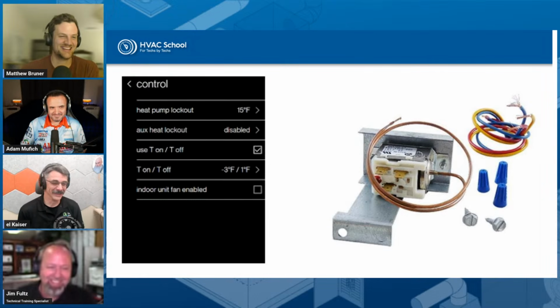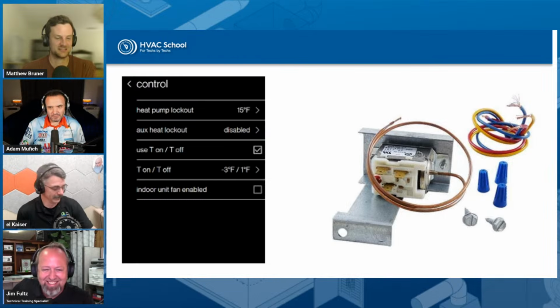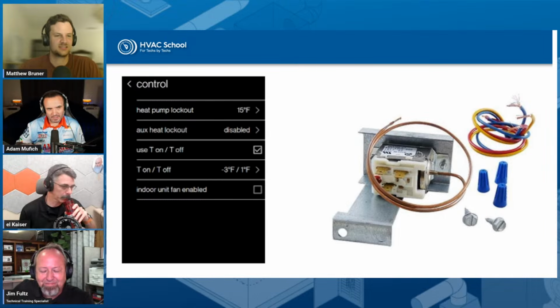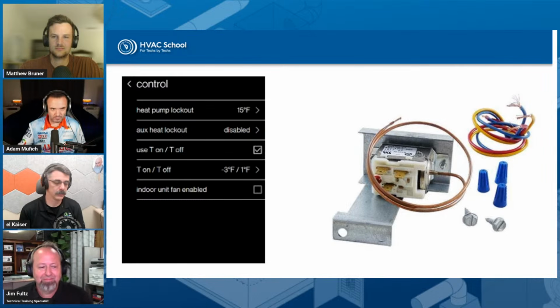I think in Manual T they refer to it as an occupied zone and an unoccupied zone, and you are not supposed to by any means blow any air into an occupied zone. It should be in a place where humans don't inhabit in the home, right? And that occupied zone is what, like 2 or 3 feet off the wall generally? I think it's 2 feet. It's like a 2-foot box around the perimeter of the room, so your walls and your ceiling. Not, you don't want to blow it on people's feet either.